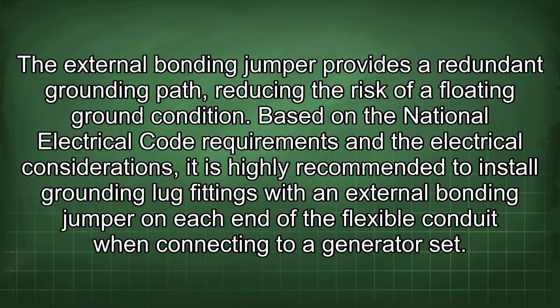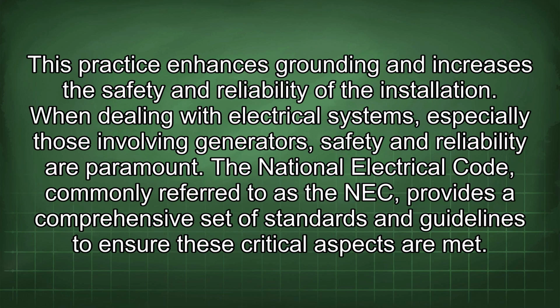Based on the National Electrical Code requirements and the electrical considerations, it is highly recommended to install grounding lug fittings with an external bonding jumper on each end of the flexible conduit when connecting to a generator set. This practice enhances grounding and increases the safety and reliability of the installation. When dealing with electrical systems, especially those involving generators, safety and reliability are paramount. The National Electrical Code, commonly referred to as the NEC, provides a comprehensive set of standards and guidelines to ensure these critical aspects are met.